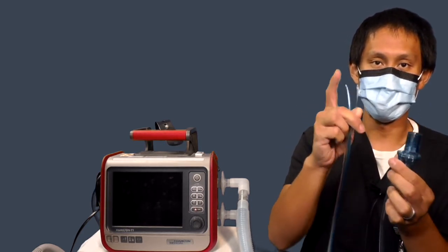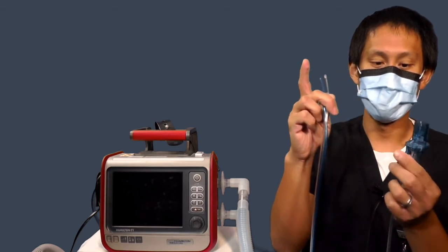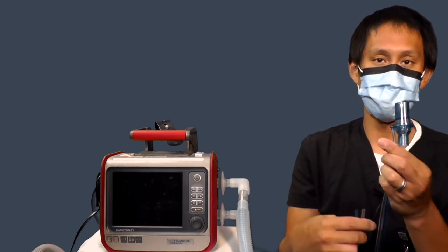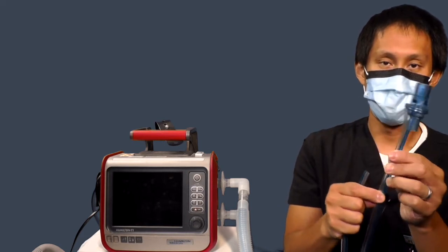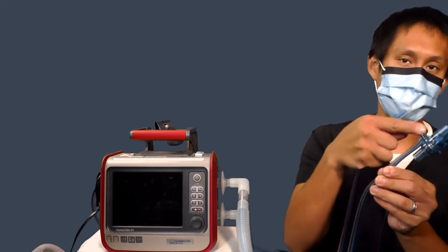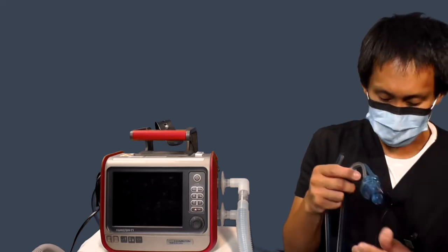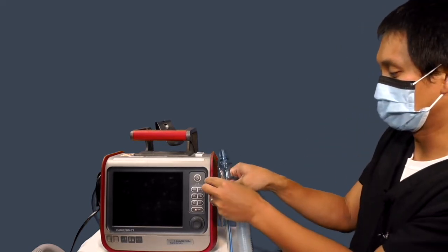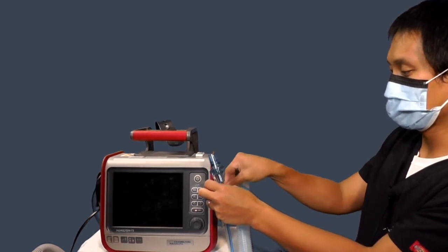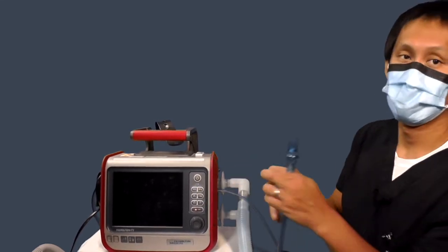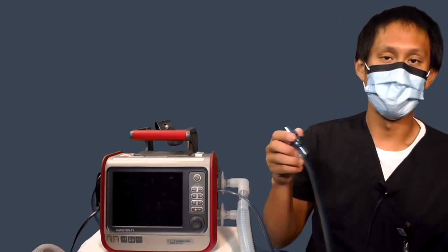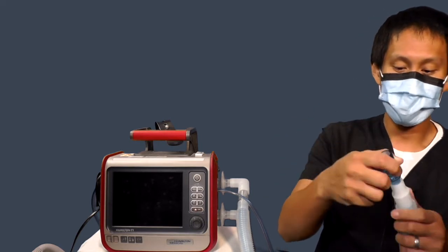So you're going to flush it back towards the flow sensor itself. Okay? So you're going to put the syringe on this end, and you're going to blow air to try to push whatever is stuck in your flow sensor back out of the sensor again. That may sometimes save you from having to open up another kit to get your flow sensor, or try to find another flow sensor itself. And after you're done, basically reconnect the flow sensor back onto your vent circuit and back onto your patient again.